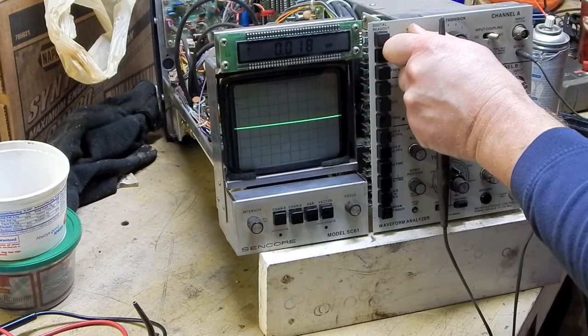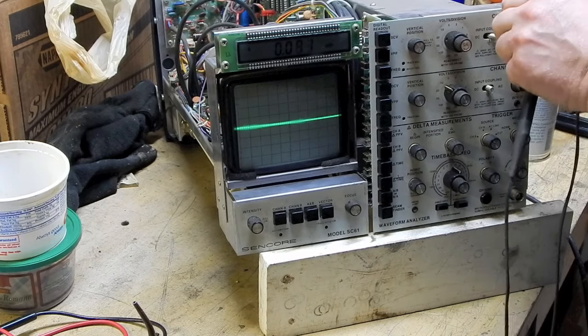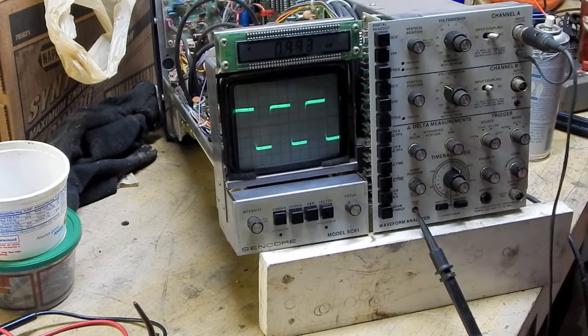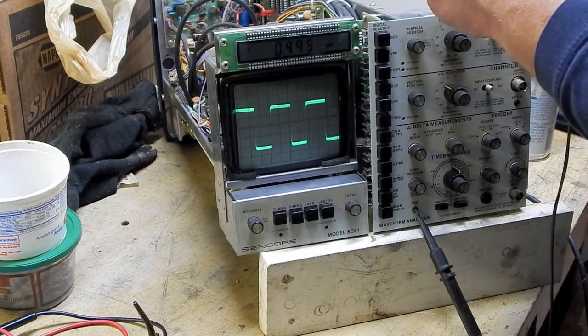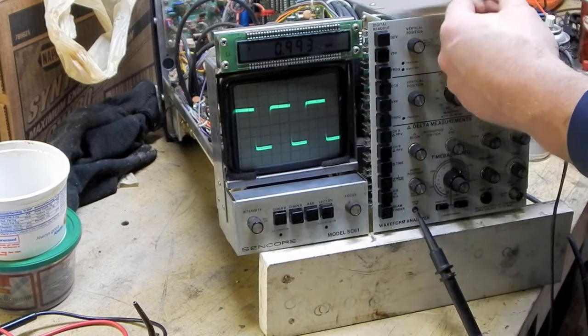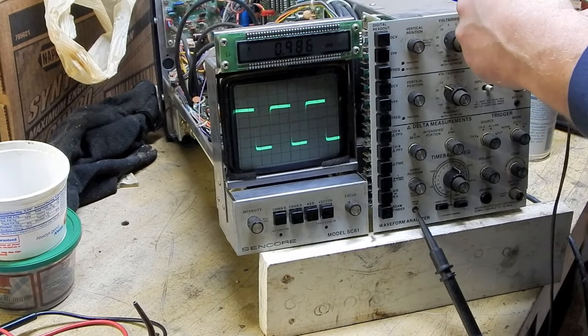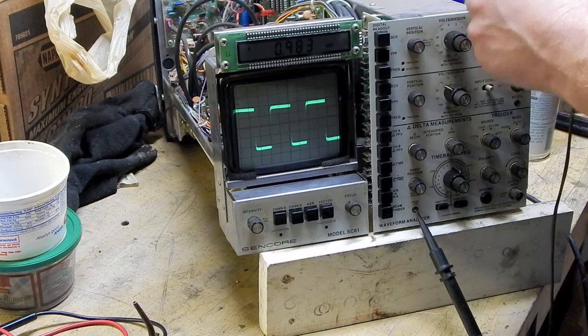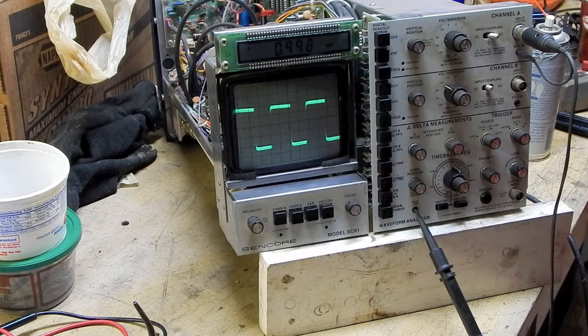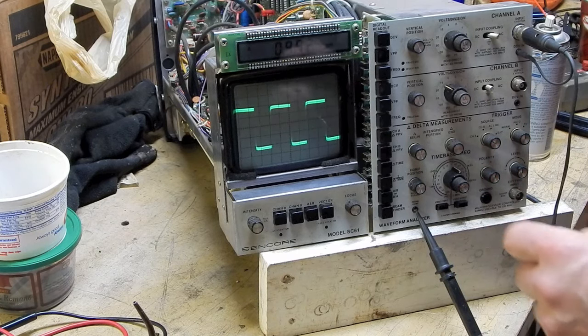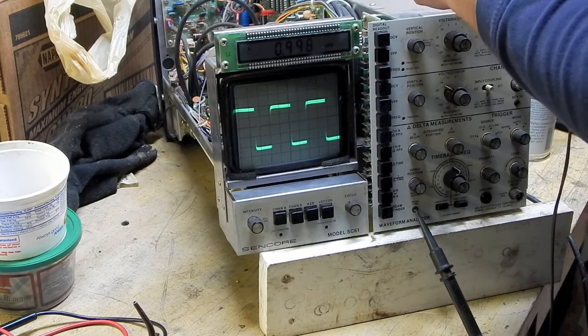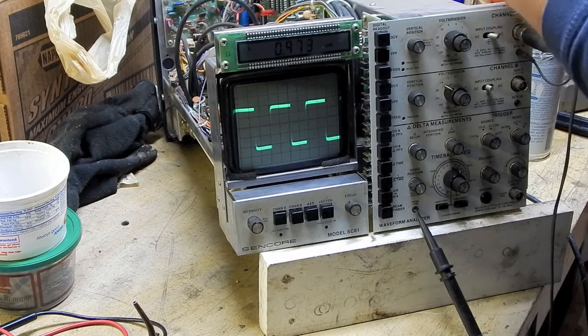So, if I put that on the reference line right there, and then I put this on, then things go squirrely. All right, so let's try that compensation screw. See if we can't clean that up. I prefer to have an insulated screwdriver to do this. Not because I'm worried about getting a shock. There's no voltage present here. Well, technically there is, but not. What I want is a screwdriver that's not going to react, because that's actually a little trim capacitor that I'm adjusting in there. All of the precision screwdrivers I have over here are huge compared to what they expect me to be using in this. There we go.